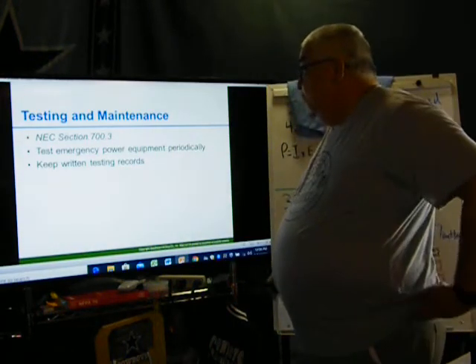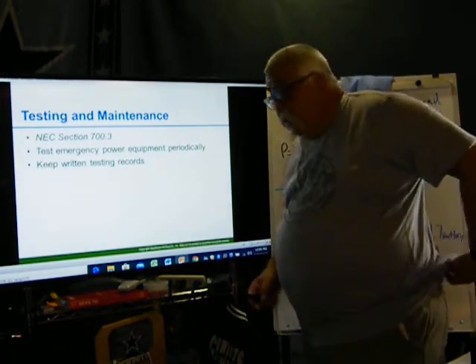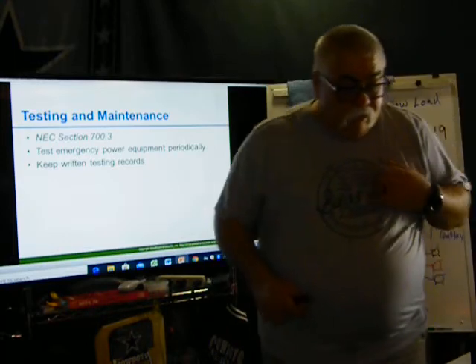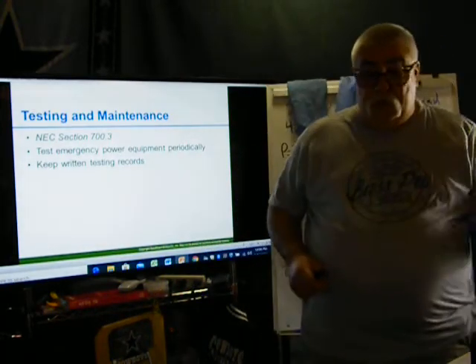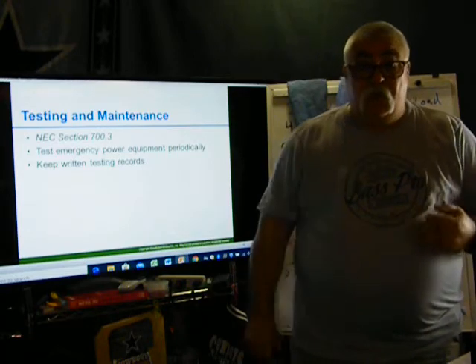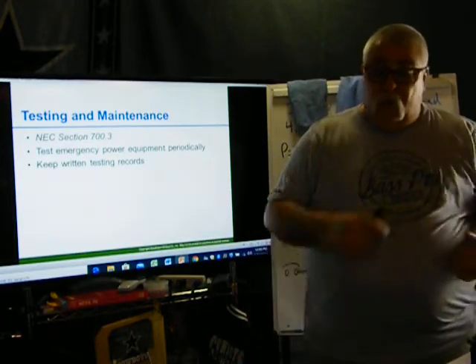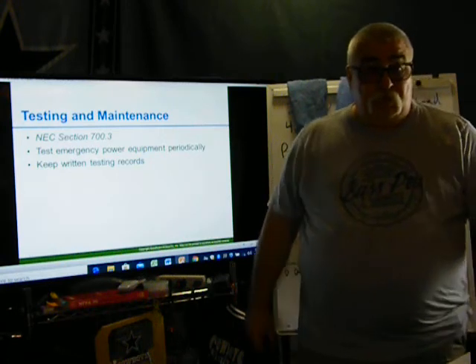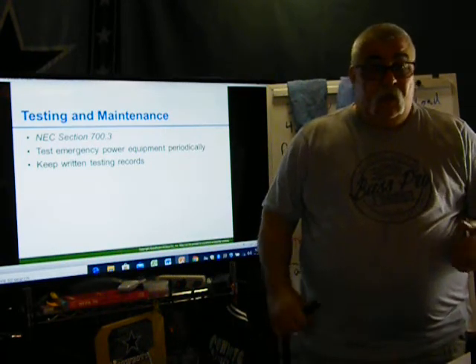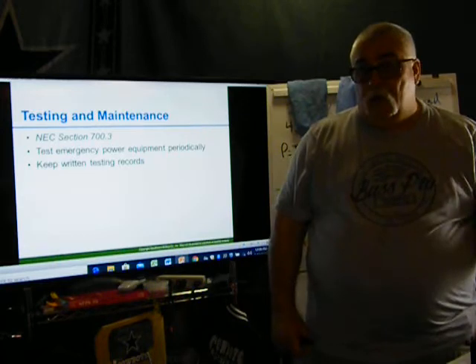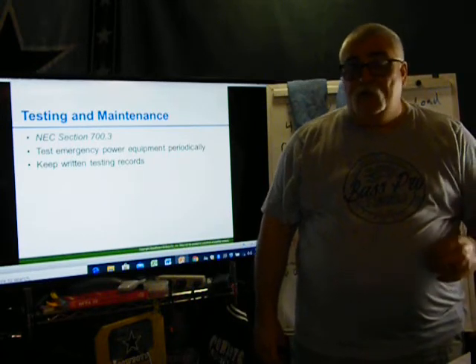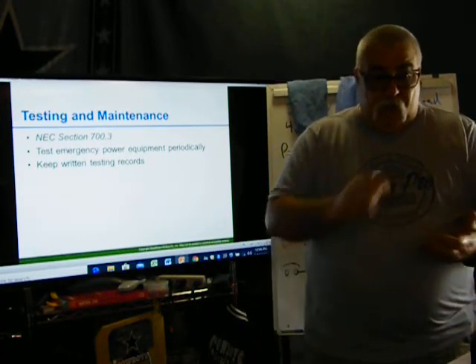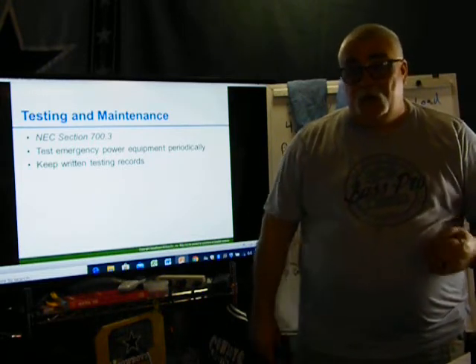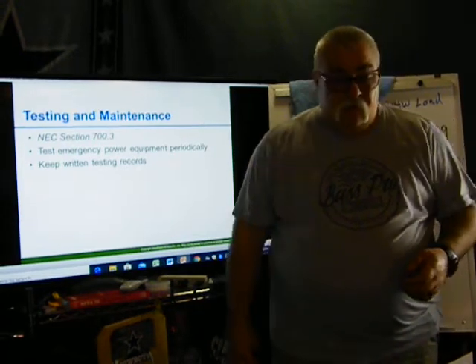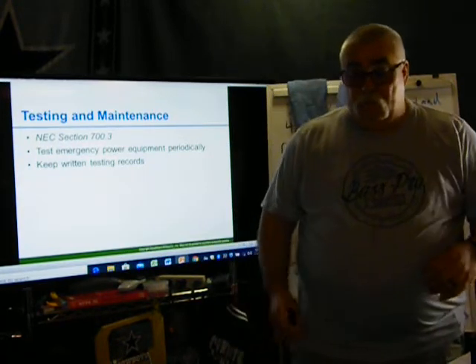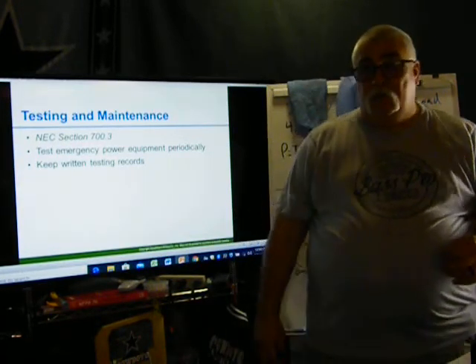Keep written records. Test emergency power equipment periodically. Keep written records. When I was working in the hospital, we had to do generator tests, and we logged down when I did the generator test. Guess what? Once a month, I had to walk through all the patient rooms and do a GFI test. Okay, and I would go back and write it down in a log. I had a log for testing GFIs. If I changed one out, I would write down that I had to change the GFI here, here, here, wherever I changed out GFIs. I also had to do a strength test on all the receptacles in the hospital.